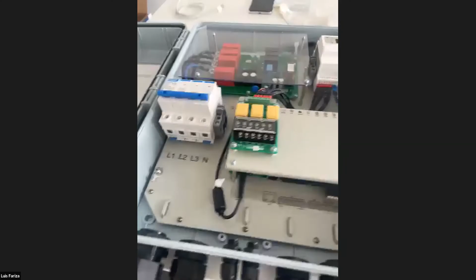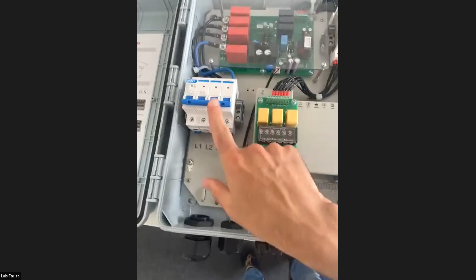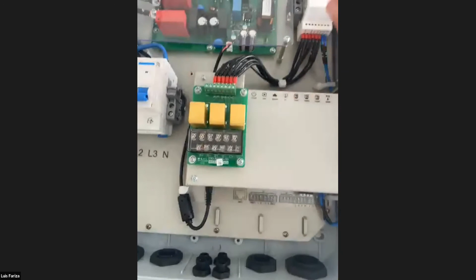And here you have the SEC 1000. You have here the AC breaker. We come here with the three lines and neutral. With this, we feed the device, the internal communication, the three-phase meter. We get the voltage here, and we get the current information from the external CT, the external current transformer that we will see in the slide right now. We connect here the three current transformers. Then we get information of the current transformer to the meter and the internal board.